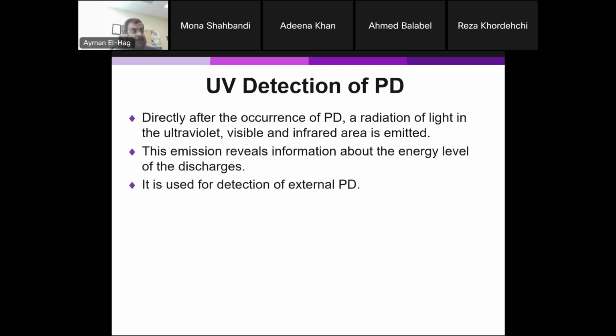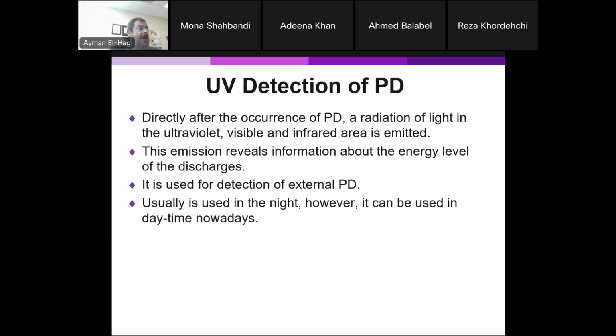It can only be used for external discharges because you have to have visible light, UV light, coming out of it. If the partial discharge is inside the transformer or inside the insulation, the defects, you won't be able to measure anything. Usually we used it, or you used to use it, at night. But nowadays, there are also corona cameras that you can use to measure the corona or the partial discharge during the day.